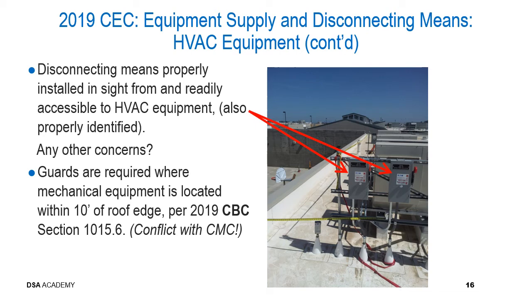So in this particular situation, obviously, these particular pieces of equipment are installed very close to the roof edge, certainly closer than 10 feet, and did require additional guardrails to be installed. So be aware of this conflict between the building code and the mechanical code, and review the plans for compliance. And if you identify that guardrails are not shown on the plans, definitely let the design team know, definitely let the district structural engineer know, and since it is a life safety issue, I would imagine and request that a construction change document is generated. And obviously the DSE is the one that's going to compel the generation of that document.